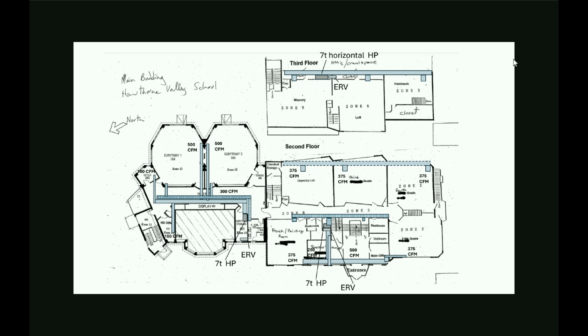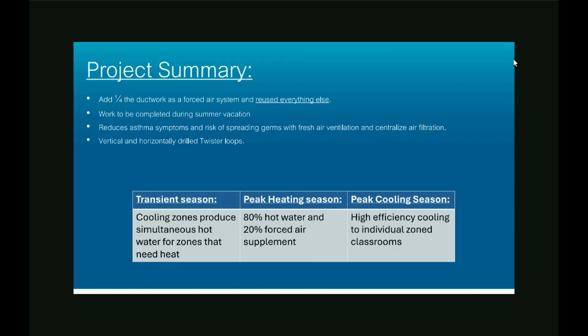CFM per ton. And the benefits of doing it this way is that we can provide chilled air, supplemental hot water, ventilation, and air filtration, all with that very, very limited duct system. And it's all done with about a quarter the size of a normal forced air system. We haven't made any other changes. We're using all the existing hot water infrastructure. Now, it is very important to have a small amount of retrofitting because it's a school. And we need to do all this work over the course of a summertime. We only have 2.5, 3 months to do it all. So doing that in a very short time frame is extremely important.